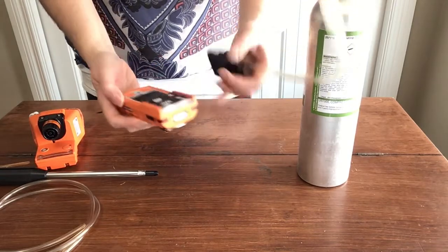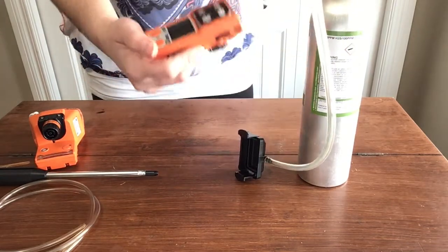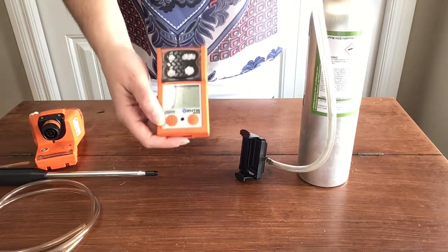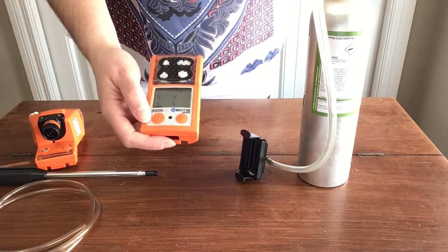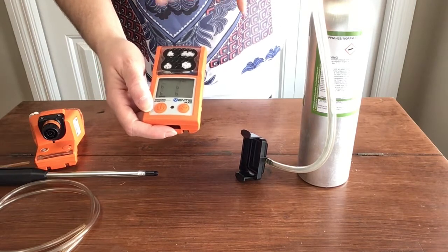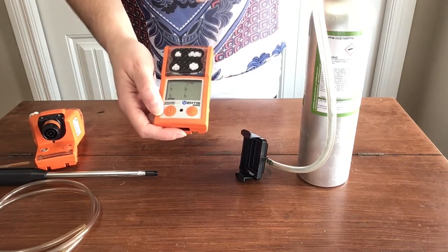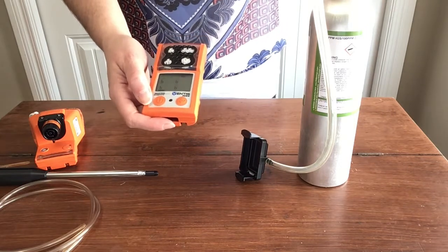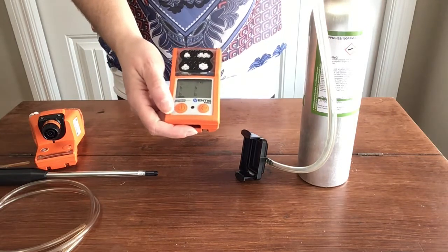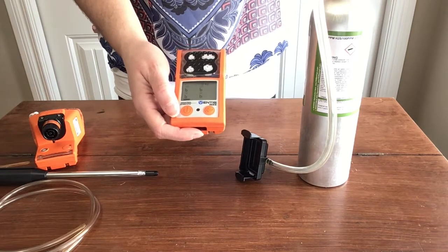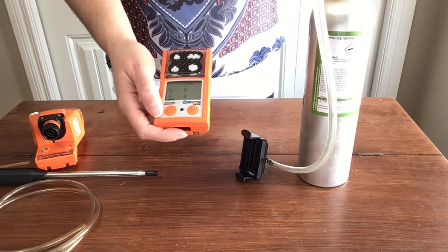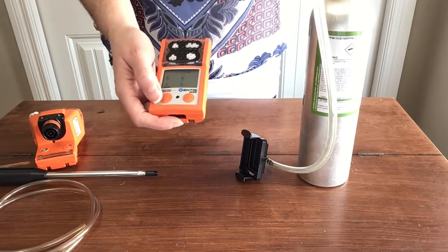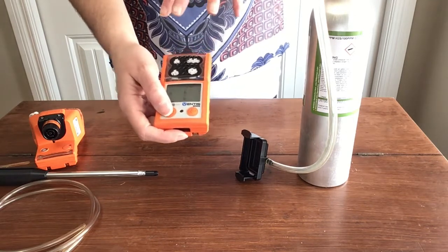So we're not going to deal with that right now. First thing we need to do is go through the fresh air zero. You cannot do a calibration on this manually unless you have it configured to do so. Same thing with the bump test. You can't get in and do a manual bump test unless you have it configured to do so. So in your configuration screen, which you can use your user manual to find out how to get into, once you're in there, if you set your bump test to 1 and set your calibration to 1, then it'll let you do a quick cal, let you do a bump test manually.